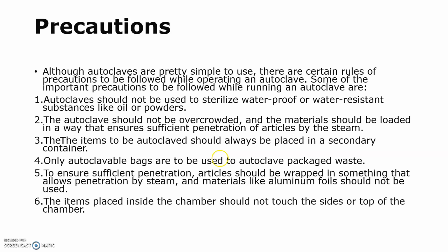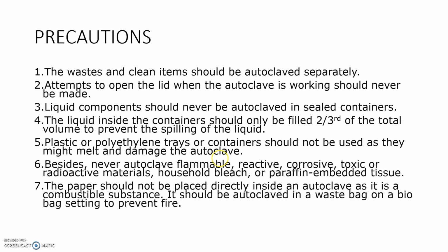The items placed inside the chamber should not touch the sides or the top of the chamber. And the wastes and the clean items should be autoclaved separately. Don't mix them. Attempts to open the lid while the autoclave is working should never be made because it leads to some sort of explosion. Liquid components should never be autoclaved in sealed containers. And the liquid inside the containers should only be filled to two-thirds of the total volume to prevent the spilling of liquid. Plastic or polyethylene trays or containers should not be used as they might melt and damage the autoclave.